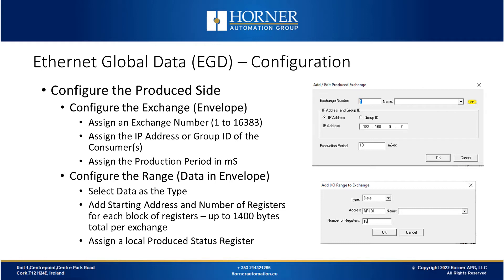Once configured, now we have to put data inside the exchange envelope. In Cscape we have a pull-down list of what can go inside the envelope. In my examples today I'll be using register based logic but it works fine with variable based logic too. We select data as the type and then set the starting address and the number of registers that we want to put inside the envelope. We can put multiple blocks of data consecutively inside the exchange envelope to a limit of 1400 bytes of data per exchange. Then we assign a local produce status register to tell us that the data is going out, but that data is not going to be sent out over the wire.